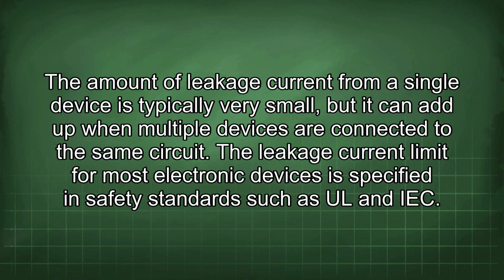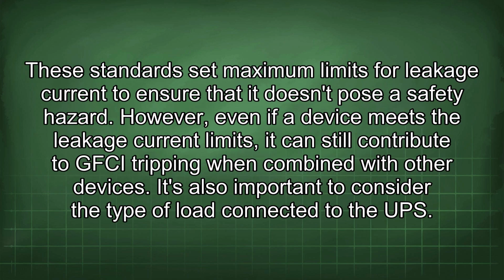The leakage current limit for most electronic devices is specified in safety standards such as UL and IEC. These standards set maximum limits for leakage current to ensure that it doesn't pose a safety hazard. However, even if a device meets the leakage current limits, it can still contribute to GFCI tripping when combined with other devices. It's also important to consider the type of load connected to the UPS.